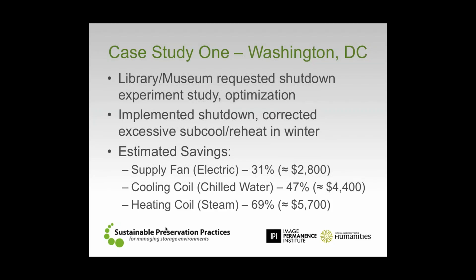And this is a case where this was one air handler that we were talking about. By looking and studying that one air handler, we realized that there were a number of other air handlers in the building that might be able to run with this same exact operation, that had these same problems with excessive subcool and reheat, and that might be possible for shutdowns. So now when you start applying some of these strategies to other air handlers through the building, those percentages are going to look fairly similar, but the actual dollar value starts to become more meaningful and more significant.